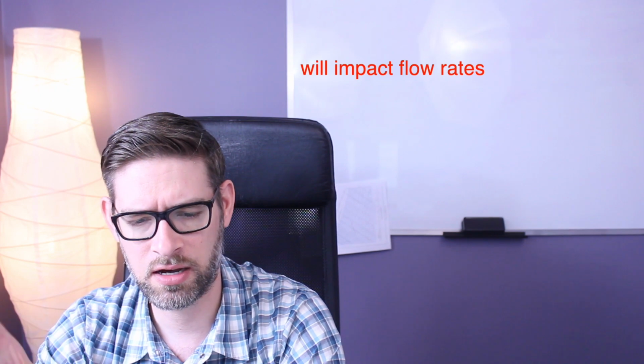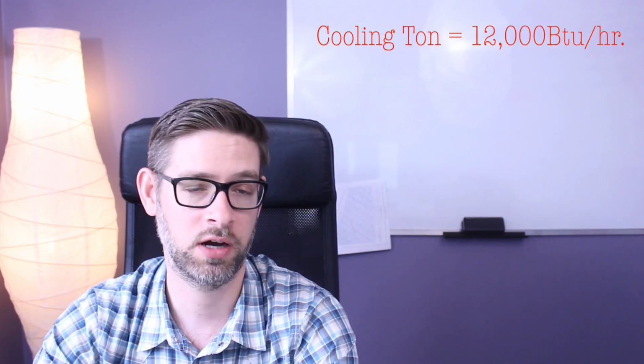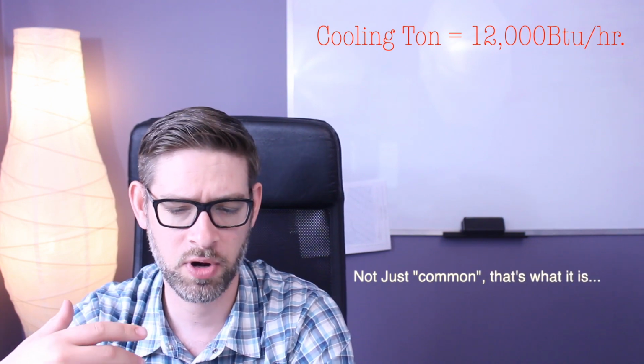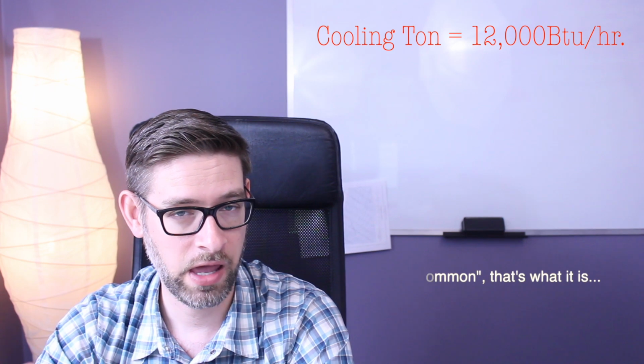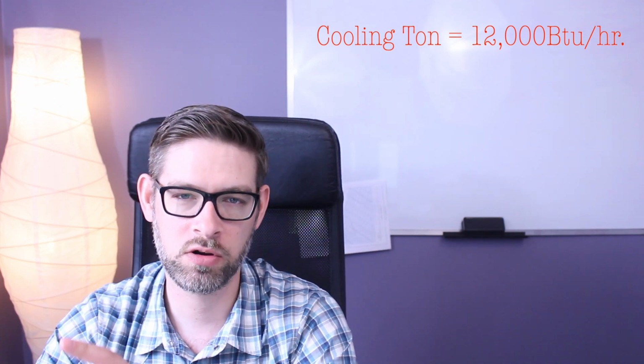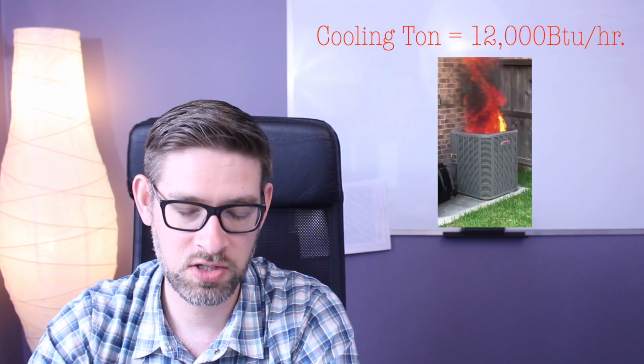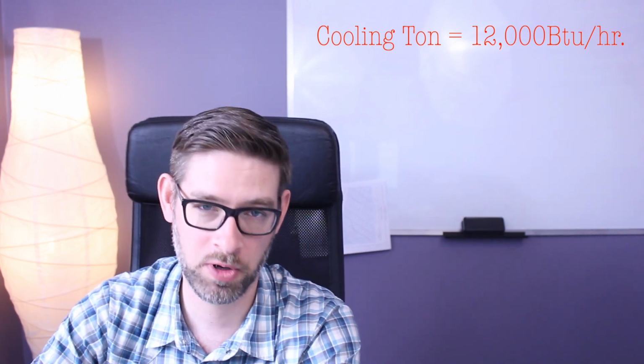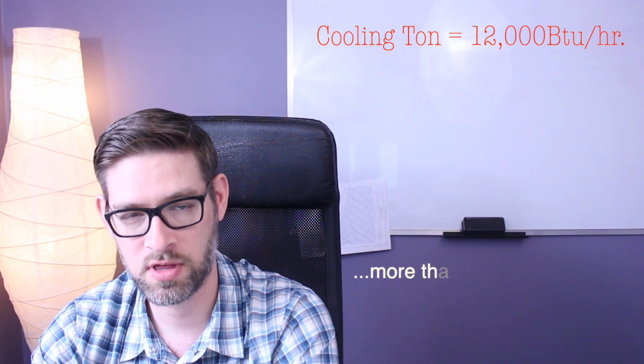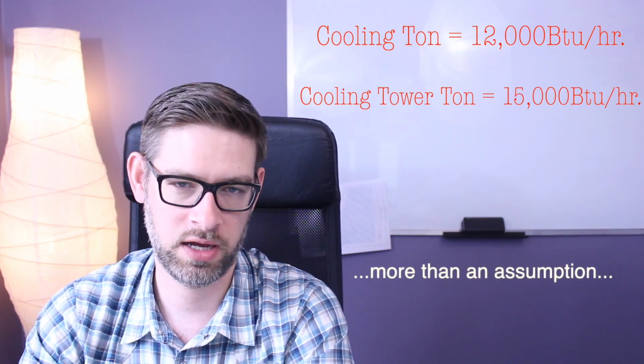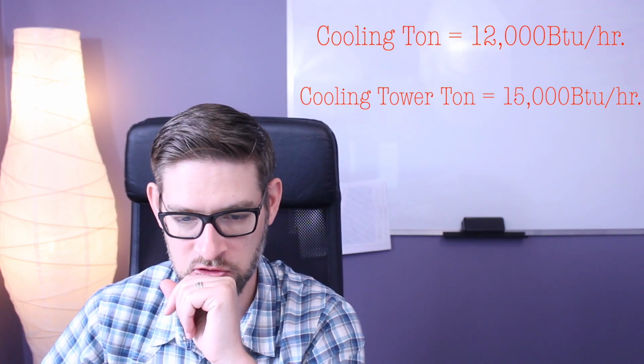Now with that, I do want to add a definition of a cooling tower ton. And I've seen this already in the last year where we're looking at a tower and someone believes that the ton, which most of us in the mechanical HVAC industry relate a cooling ton to, is 12,000 BTUs per hour. One ton is 12,000 BTUs per hour, and that's pretty common. And so it's easy to get tripped up on this because the cooling tower is dealing with the condenser water. And when we're looking at condenser water, we also have to take into account the heat of compression. So the heat from the motor in the compressor is being rejected into that condenser water, as well as the energy from the building, right, through the cooling coils. So 12,000 BTUs plus the heat of compression, which we have assumed at 3,000 BTUs per hour, gives us a cooling tower ton at 15,000 BTUs per hour. So a little bit different than what we're used to.